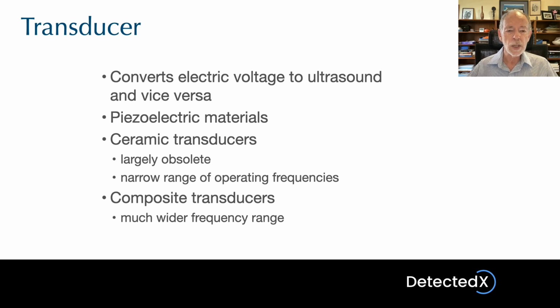So now other materials are used, and often the transducers are what are referred to as composite transducers, and these operate over a far wider range of operating frequencies. So in the past, transducers may have been referred to as 5 MHz transducers or 3 MHz transducers. But now you're more likely to have a transducer that will operate from 3 MHz up to 8, for example, or 5 up to 12. So you get a wide range of operating frequencies in any one probe.